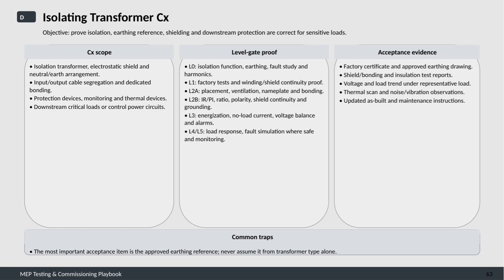Starting with L0, we verify isolation functions, earthing, fault studies, and harmonics. L1 covers factory testing and proving winding and shield continuity. L2A checks installation details like placement, ventilation, nameplates, and bonding, while L2B confirms insulation resistance, ratios, polarity, shield continuity, and grounding. At L3, energization tests are done, including no-load current and voltage balance, alongside alarm verification. Finally, L4 and L5 focus on load response, fault simulation when safe, and ongoing monitoring.